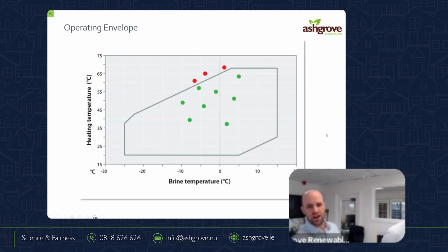Yeah, and I suppose important to note there that the design of this is within our control. So the brine temperature is within our control for a ground source system, because we can design the amount of pipe that goes into the ground to collect the energy. And our heating temperature can be designed for our heating distribution system. So larger radiators in a domestic house, for example, don't need as high an operating temperature as smaller radiators do, depending on the room. Yeah. So this is all within our control, this heating envelope, and understanding it is important for designing the elements that surround the heat pump. Yeah. And again, not blaming the heat pump for not performing when we've clearly put a system in place that we're expecting to do something outside of its operating envelope.